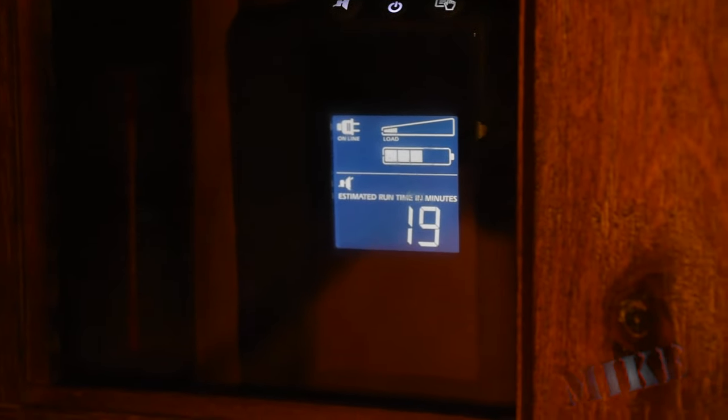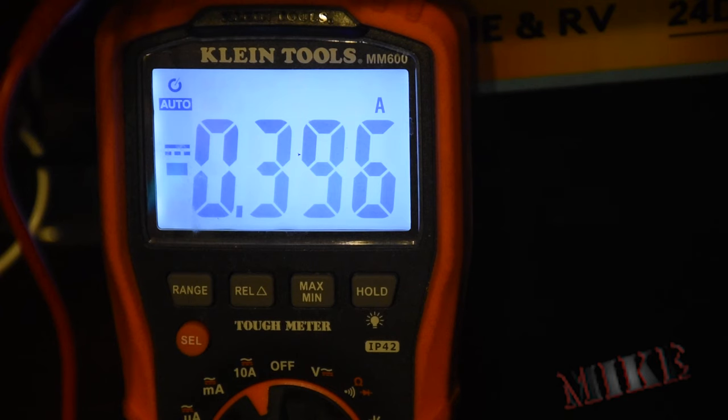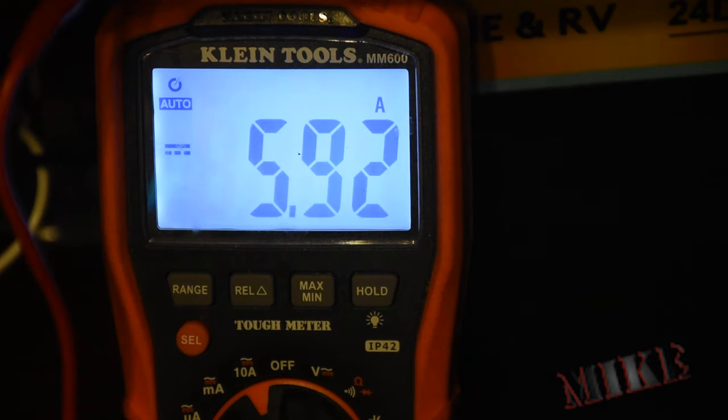We just won't obey the meter at the moment. We know that it's lying to us because the UPS really has no idea how big these batteries really are. Now on battery, it's pulling more amps than I expected, but still below the 10 amp fuse. So we're good.